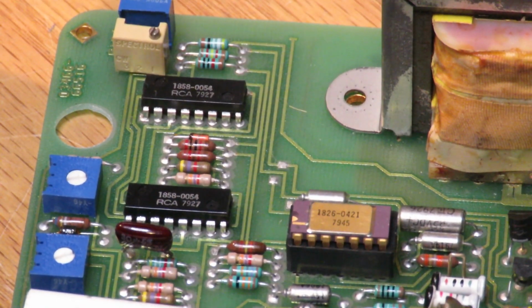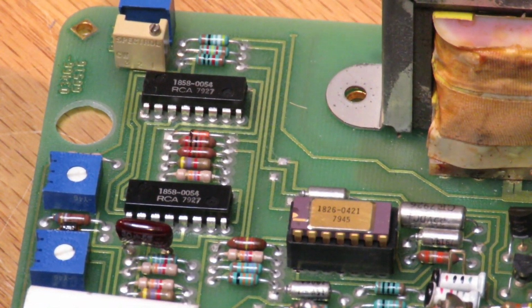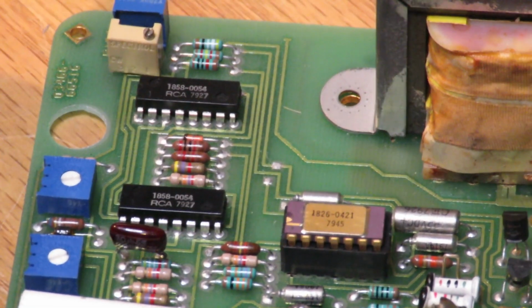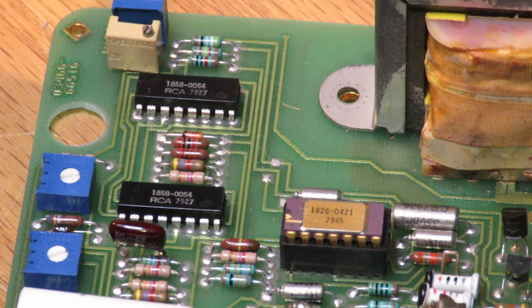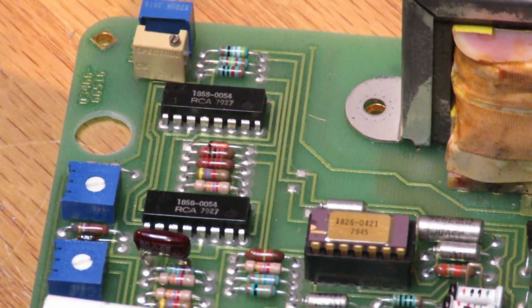Next up are these 2 ICs, and I'm pretty sure that's where the problem with this device is. Those 2 ICs form a comparator, so the output of the integrator gets compared to ground, and if it's above or below, they close the loop on it. That's how the dual slope A to D works.